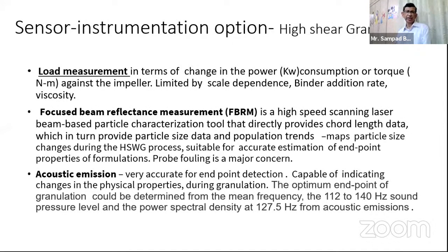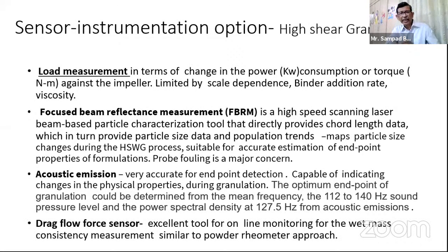Acoustic emission is very accurate for endpoint detection, capable of good indication, and commercial equipment is being used especially in UK and Europe, where it is quietly in use. It actually measures the sound generated at a particular frequency range, and the sound pressure is measured. The change in acoustic emission tells you about the granulation change point and endpoint, and also gives some indication about physical properties, which can be mapped and controlled through chemometrics.